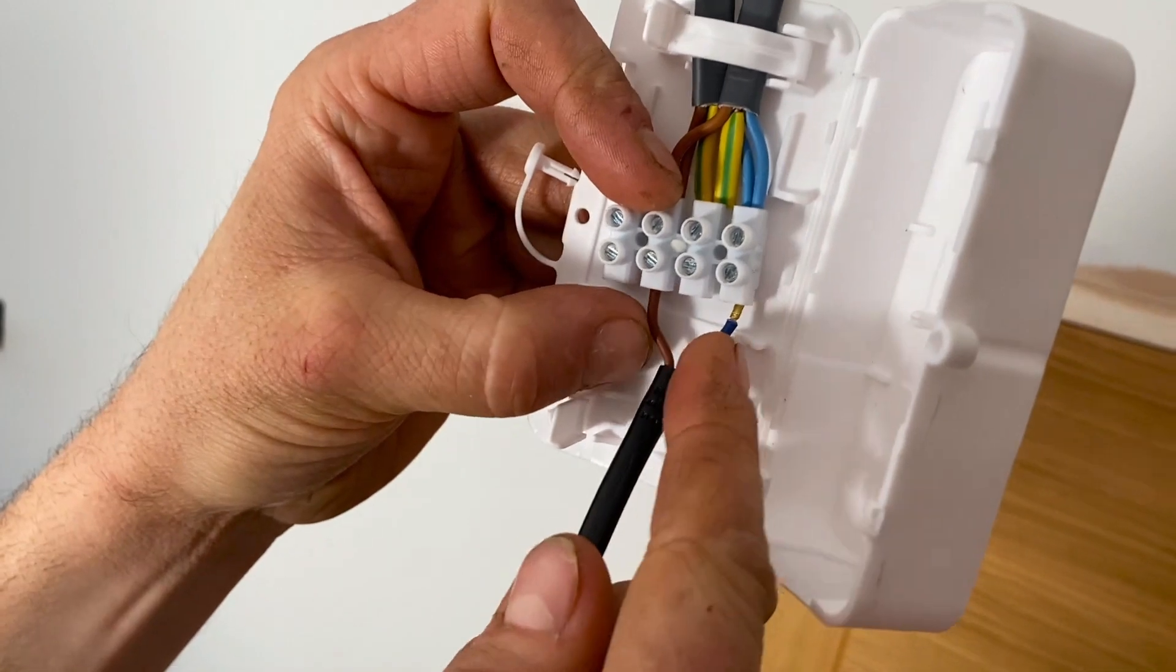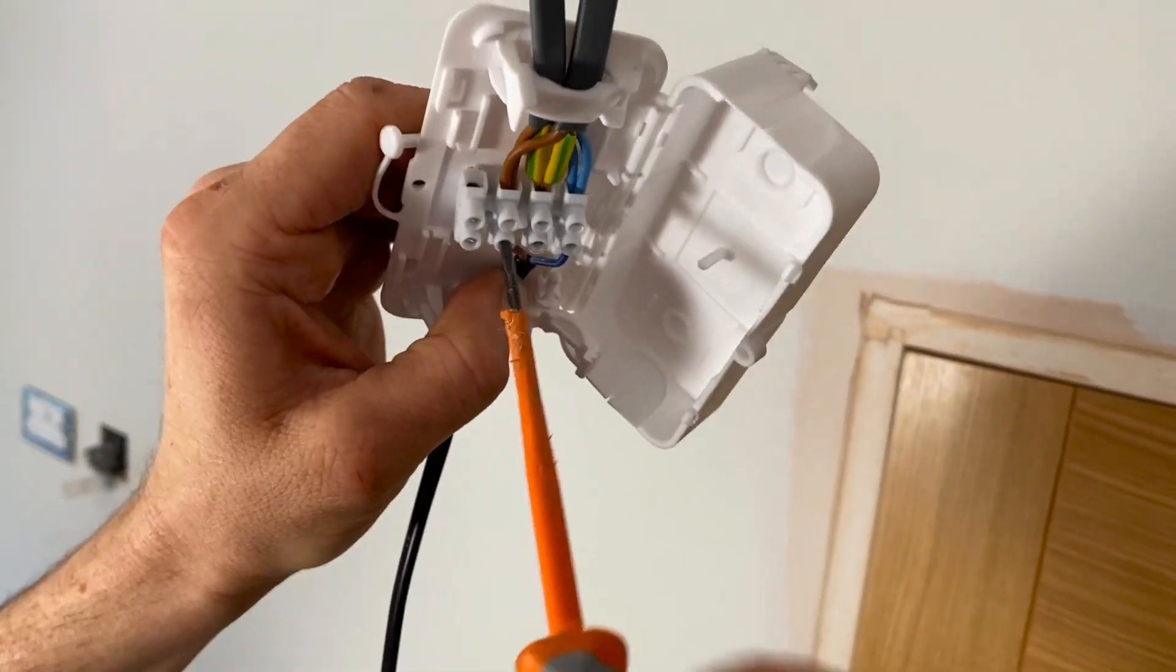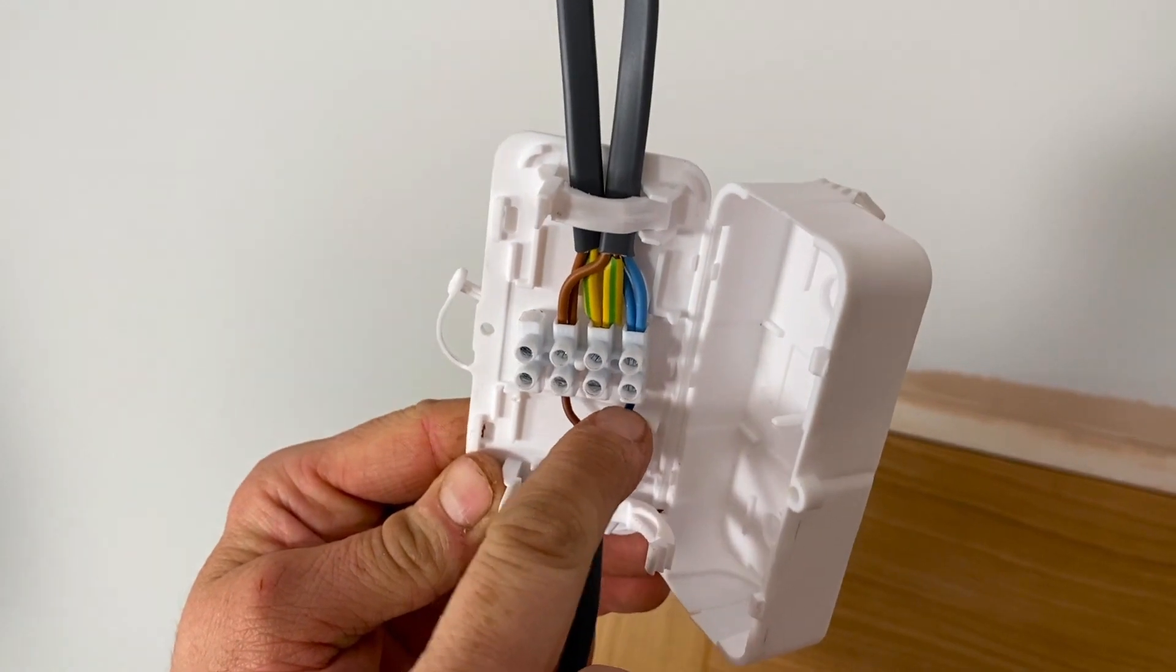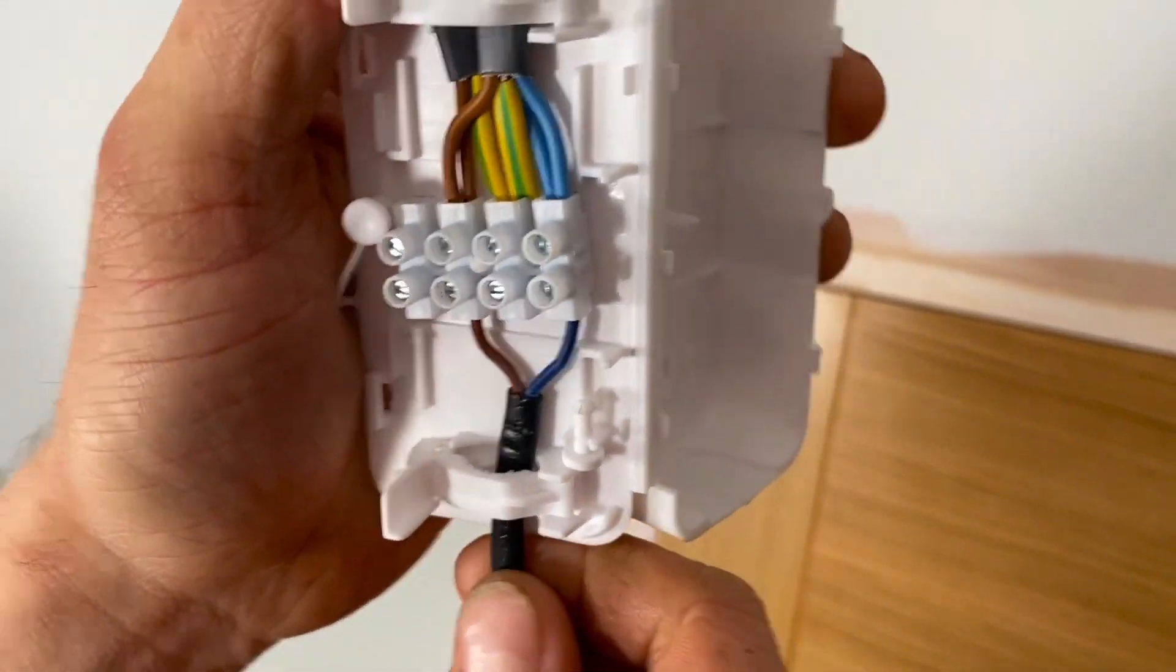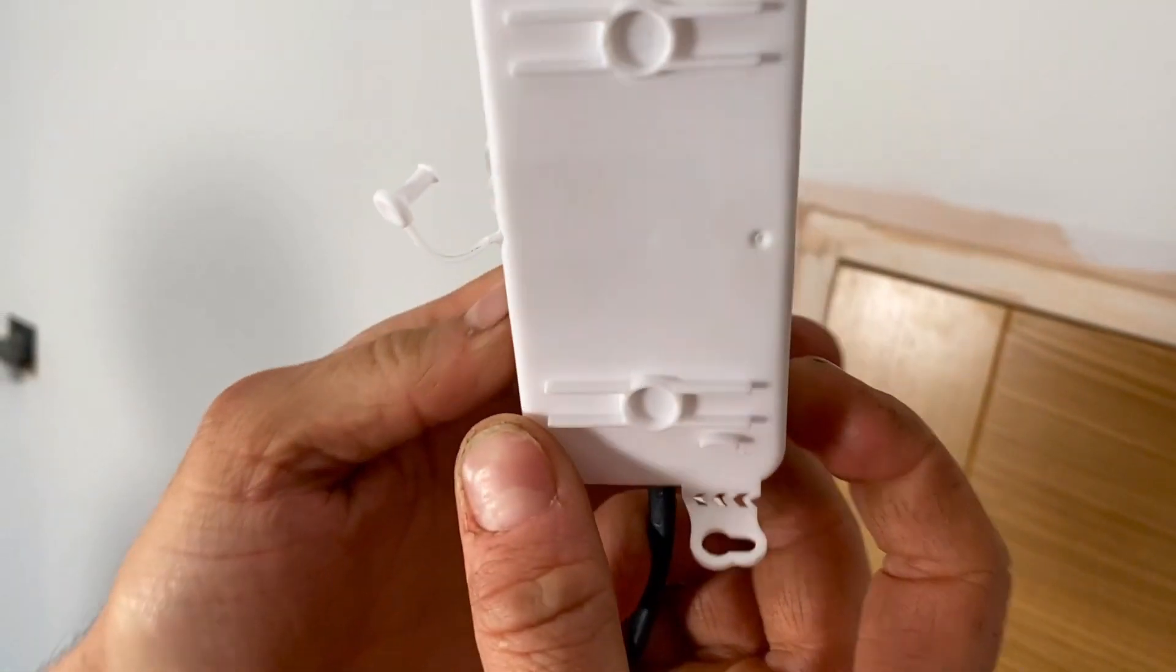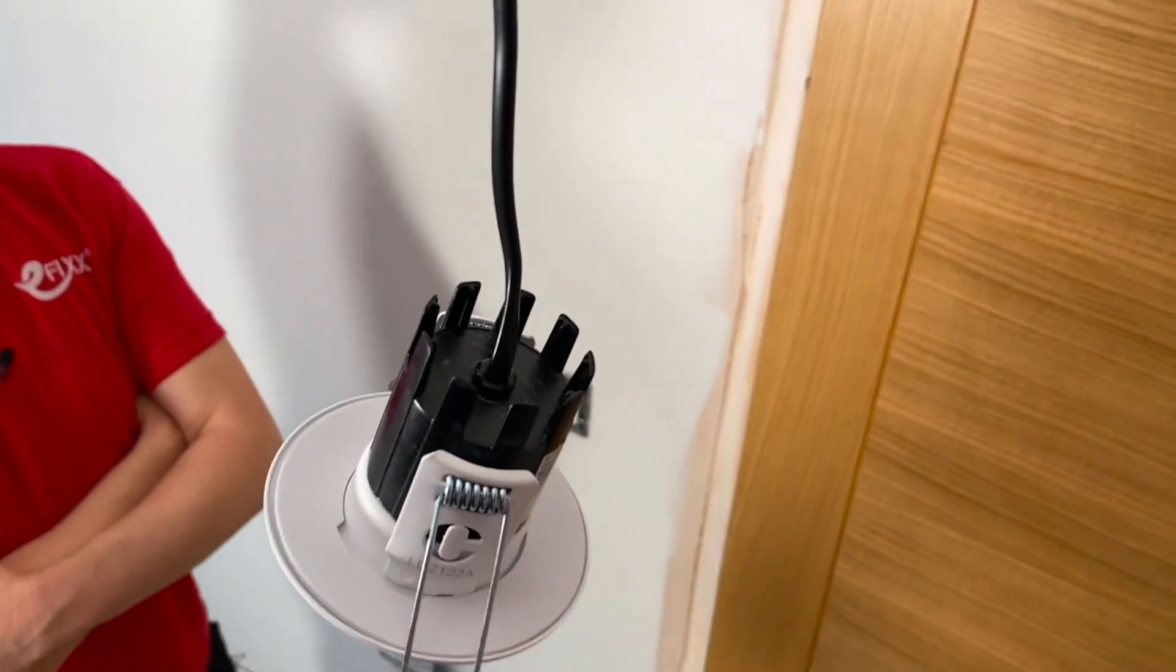We'll now get the spotlight. So we're putting in the connections for the spotlight now for the recessed downlight. Bent into place for easy fitting. Obviously clamp down with your thumb to make sure they stay in place. It's nice and adaptable, this box, because you've got two different kinds of cable coming in and out, a different number on each side, and that cable grip again, that's going to clamp down to different thicknesses of cable. When you close up the outside, really nice is that it just clips closed, so you've not got a tool again to worry about. And then we've got the lock-in pin for that extra bit of security. Obviously, this isn't a maintenance-free connector because it's got the screw terminals, but perfectly suitable for the situation that we're installing here.